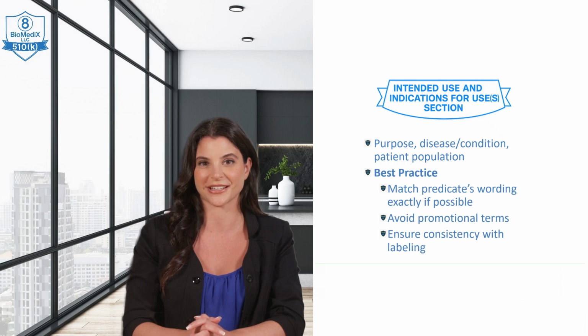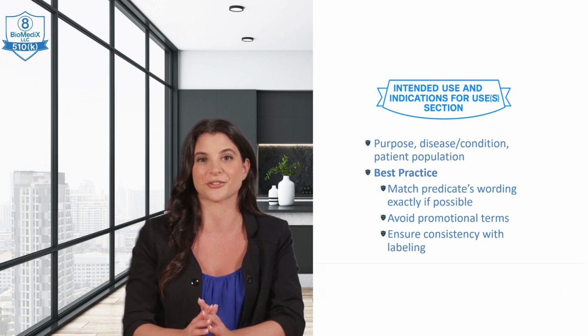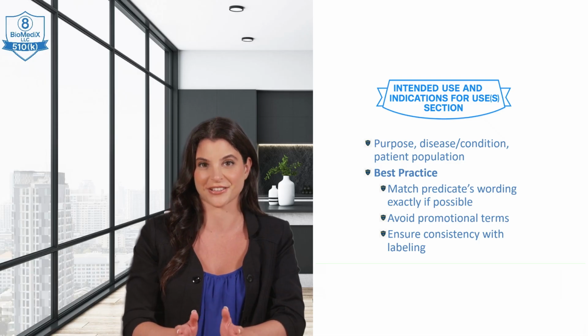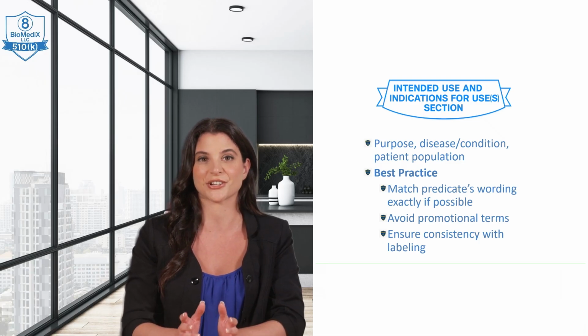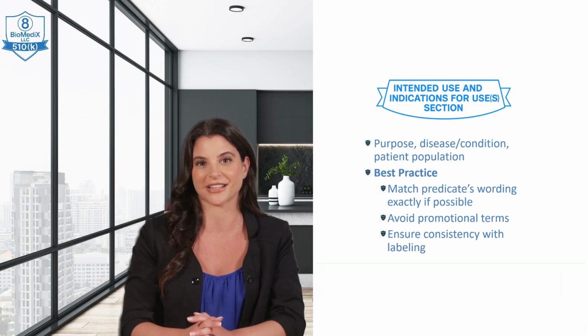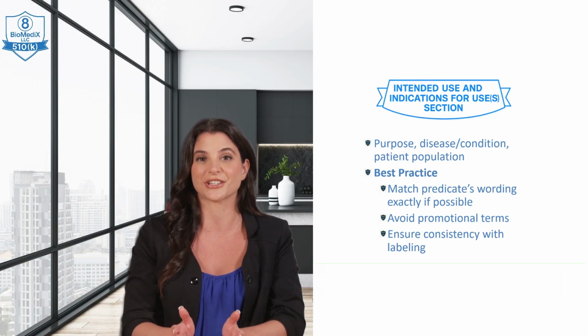Section 2. Intended use and indications for use. Let's break it down by requirement, then best practice. First, we tackle intended use and indications for use. The requirement is to describe the general purpose of the device and the specific disease or condition it will diagnose, treat, prevent, mitigate, or cure, including the patient population for which it's intended. This must be consistent throughout your entire submission, especially with your proposed labeling.